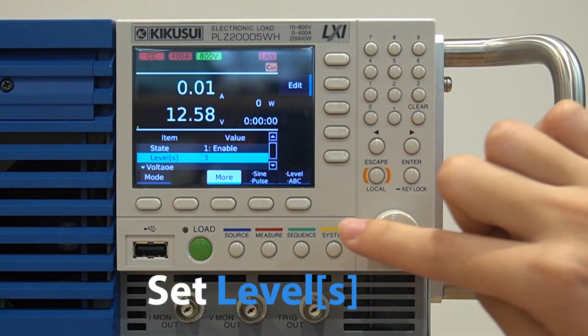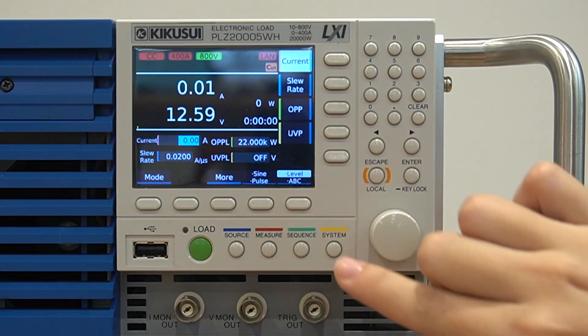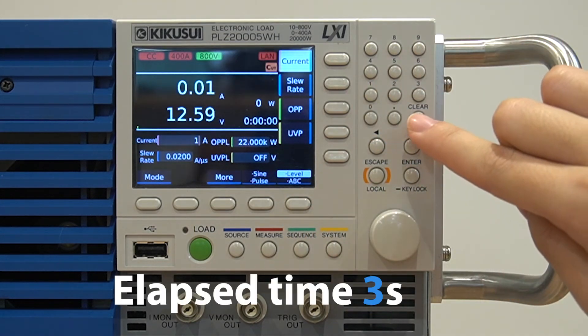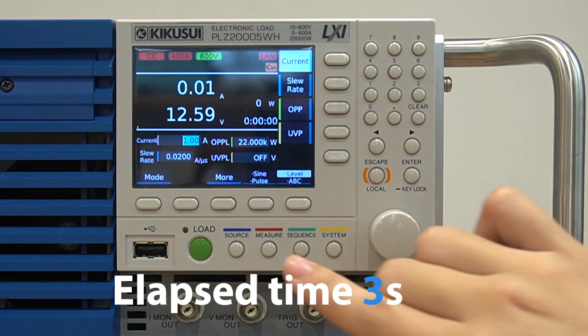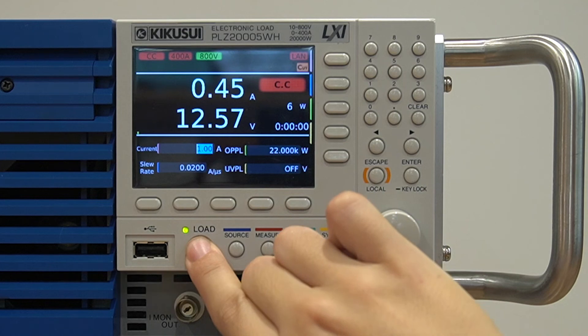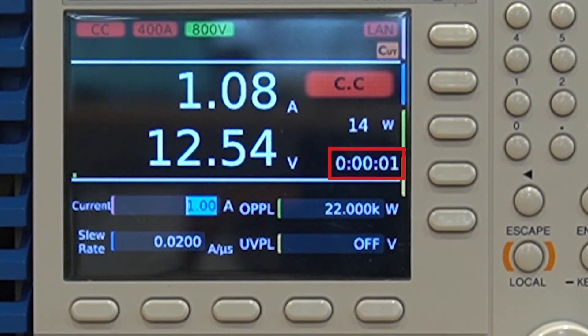Lastly, input your desired setting range for your cutoff item and press Enter. Once you do this, the PLZ20005WH will automatically cut off at your specified cutoff point in order to minimize damage to your DUT due to over-discharging.